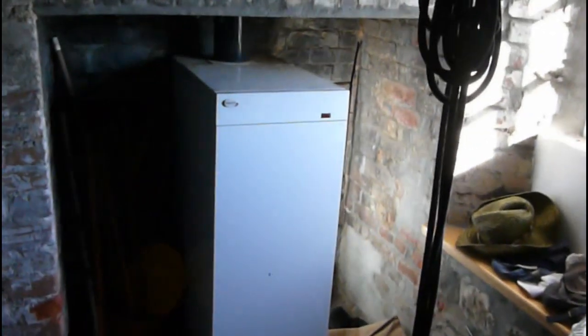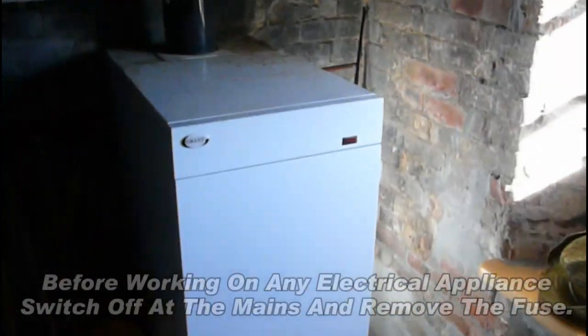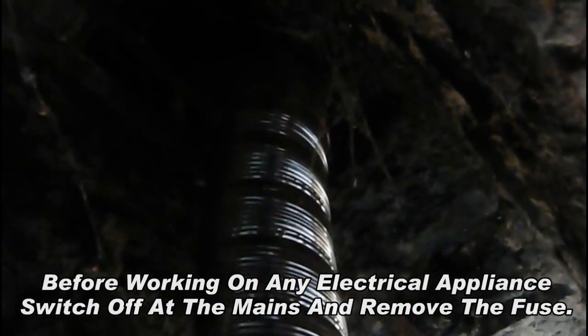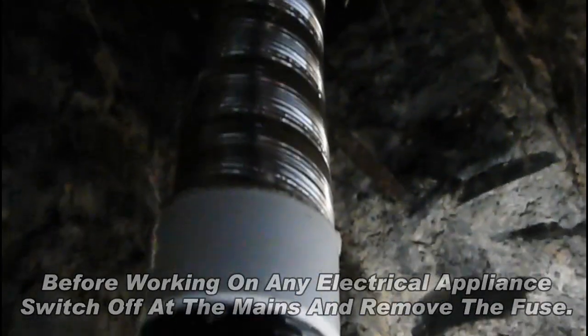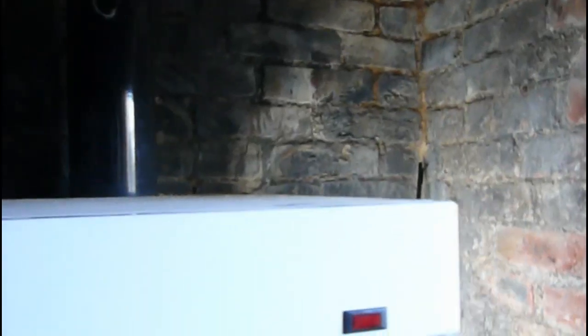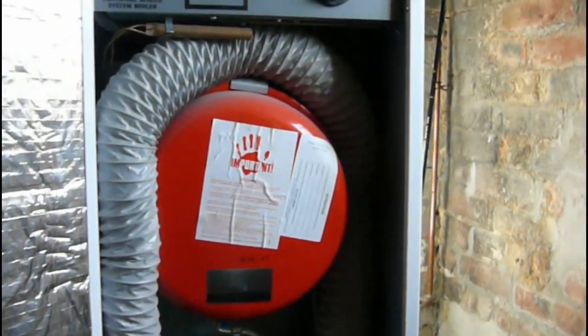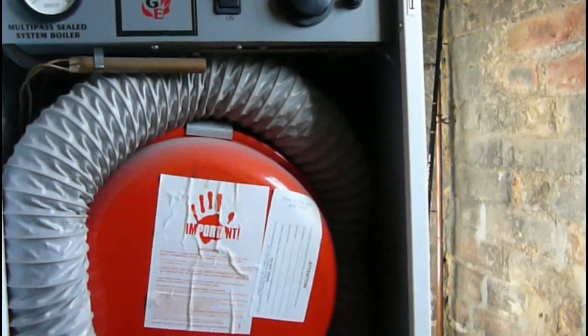One of the jobs today is to clean this oil-fired boiler flue. There's a flexible liner there, no closure plate, and as you can see, no inspection in the flue pipe. It's a condensing boiler with no access through the baffles.